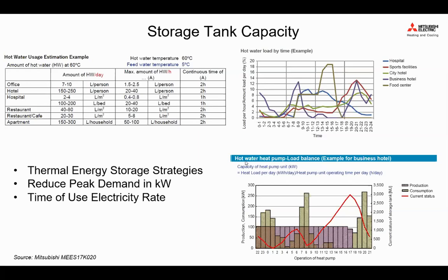And then there's an example here you can see for a hospital, for a sports facility, let's say a gymnasium or a YMCA, or a city hotel. You can see the hot water demand is not a flat line throughout the day. There is a certain period that people will use the most hot water, and we'll be able to take advantage of that based on different studies and different runs. And then on the bottom right-hand corner you can see how much hot water is being produced, how much is being consumed, and what the status of hot water inside your tank is to accommodate the load.